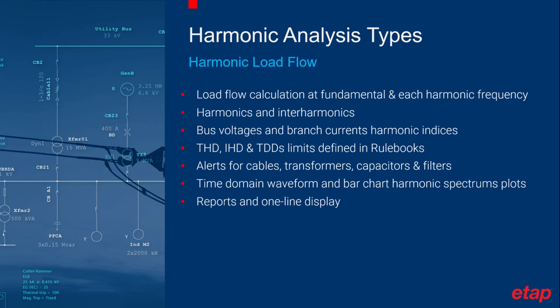If any violations are detected or element capacities are exceeded, they will be shown in the harmonic load flow analysis alert view. These results can be viewed directly from the one-line diagram using the harmonic load flow slider and the harmonic display options editor. Plots are available to show both voltage and current waveforms in time domain and the harmonic spectrums in bar charts. Input and output reports are also available. Now let's see it in ETAP.